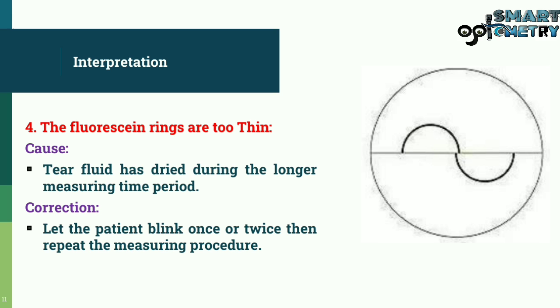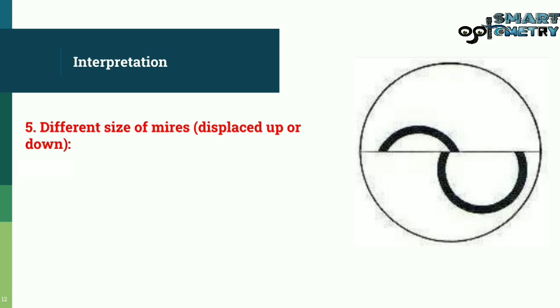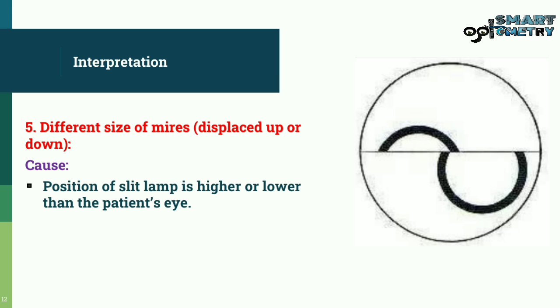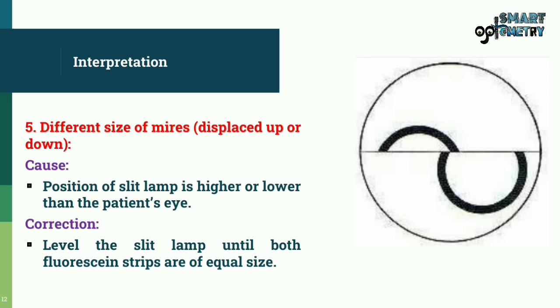Different sizes of mires displaced up or down indicate the position of the slit lamp is higher or lower than the patient's eye. Correction is to level the slit lamp until both fluorescein strips are of equal size.